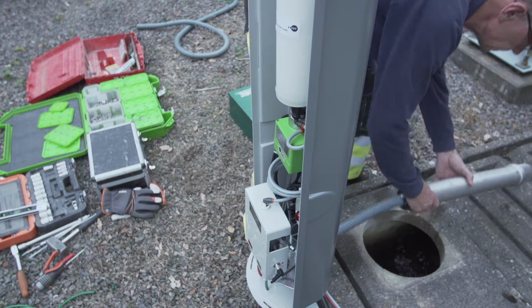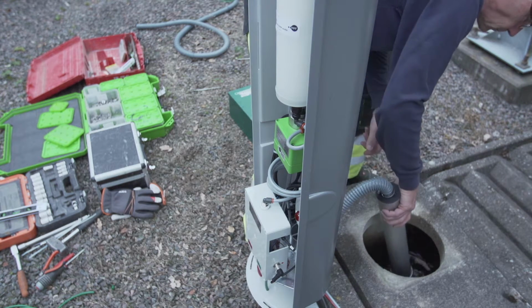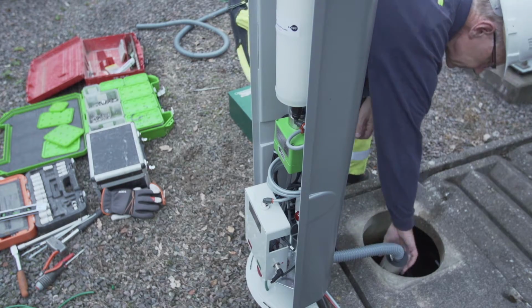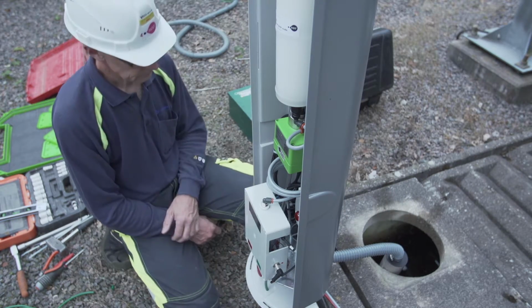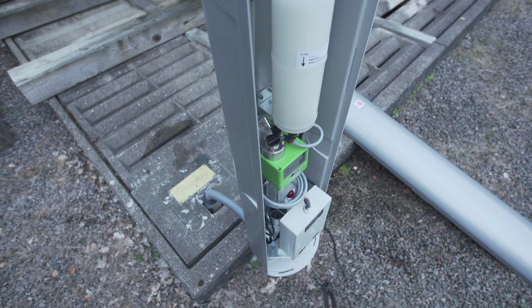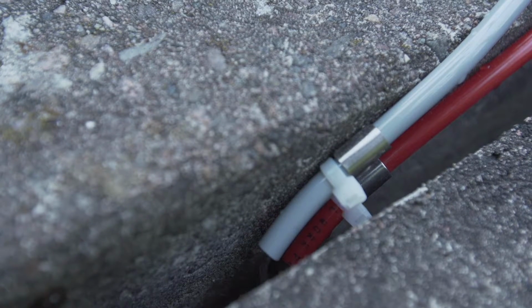Lower the suction unit into the water and verify functionality of pump, solenoid valves, flow meter, measuring cell, and level sensor manually. Complete the commissioning by a hard reset. If the water level is over the threshold, the unit will automatically start a discharge.